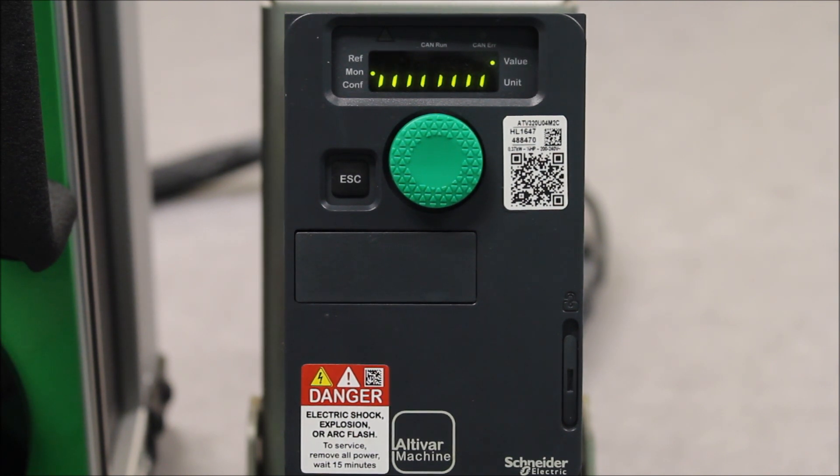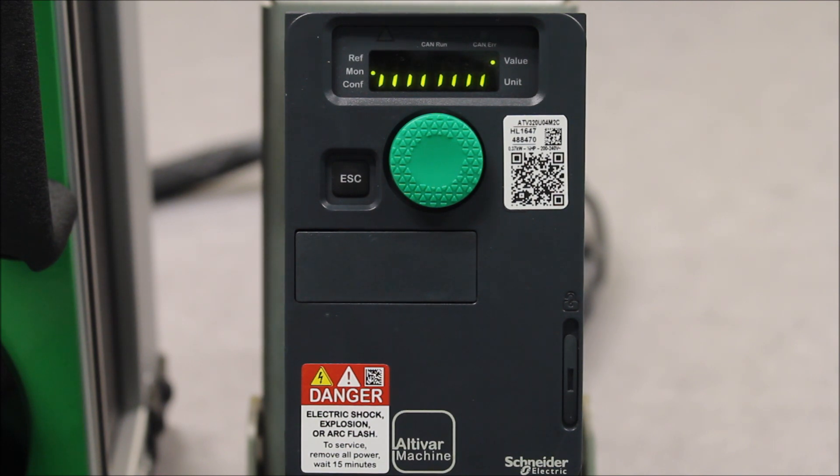Same thing with DI2, DI3, 4, 5, 6, and so on. That's basically how you can tell whether your digital inputs are getting a signal or not, and that might be a good tool to know if your run command is coming in, if you have a wiring problem, if it's a programming issue, whatever have you.